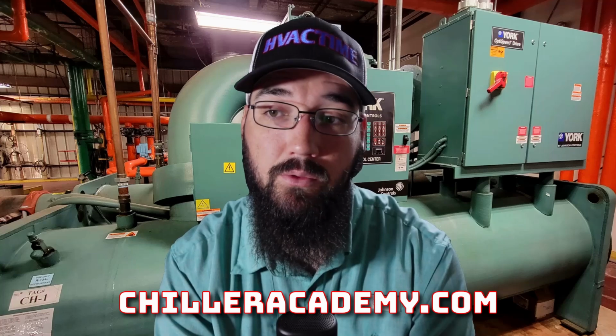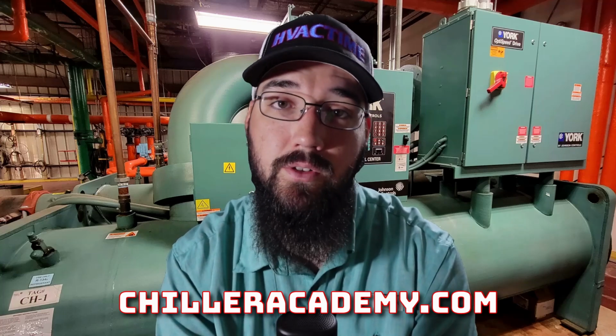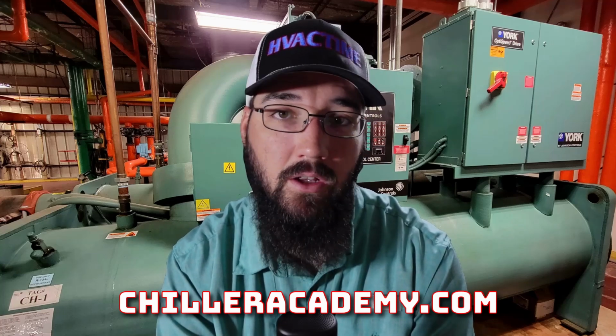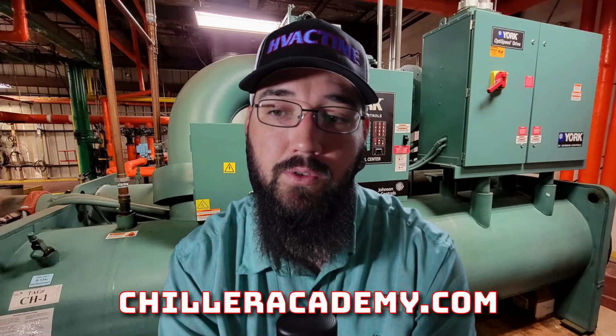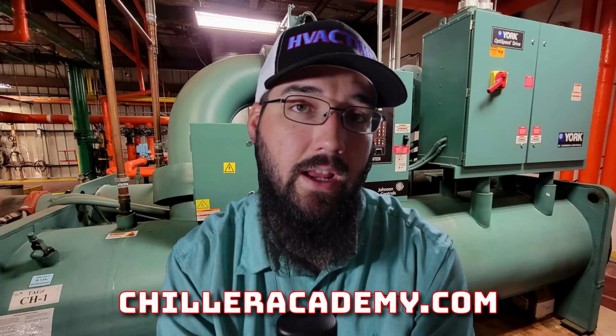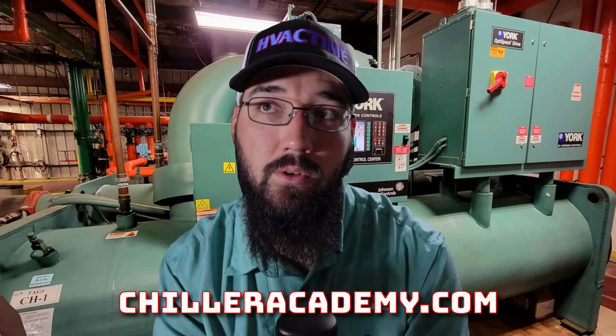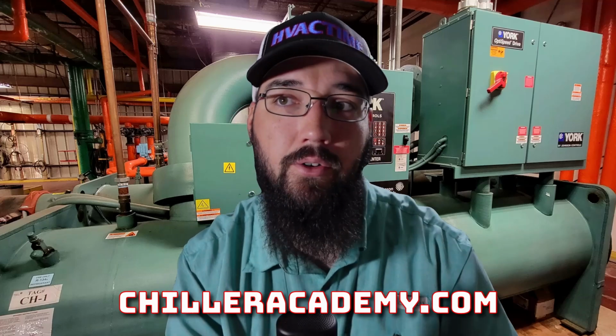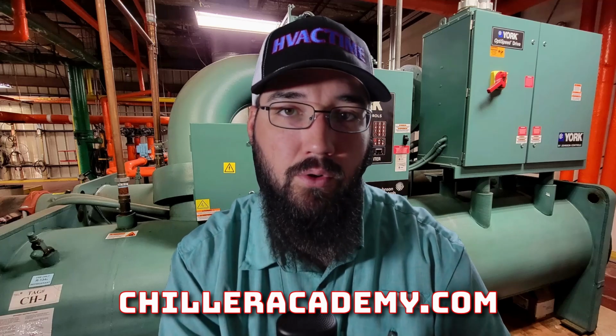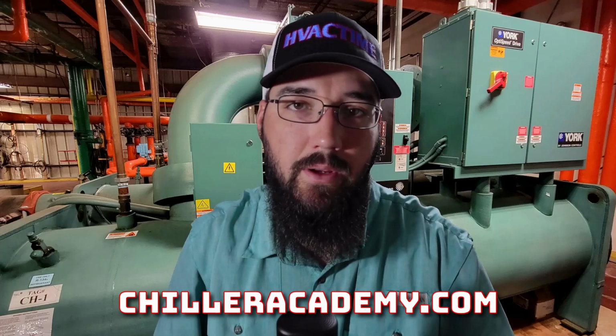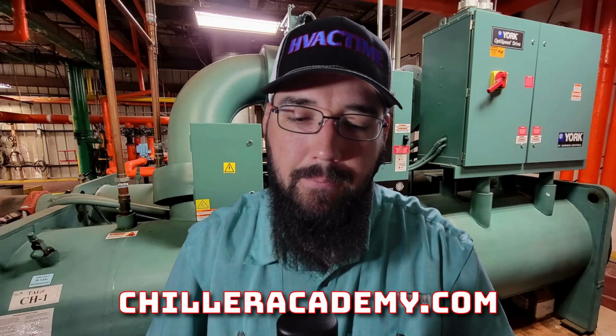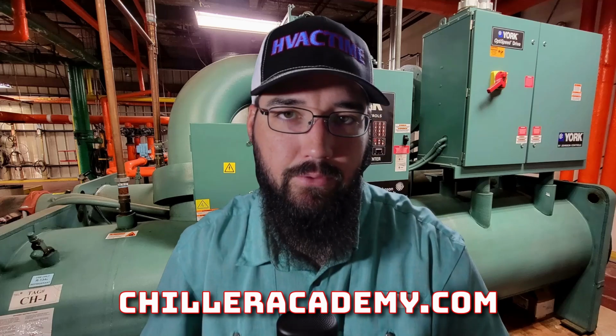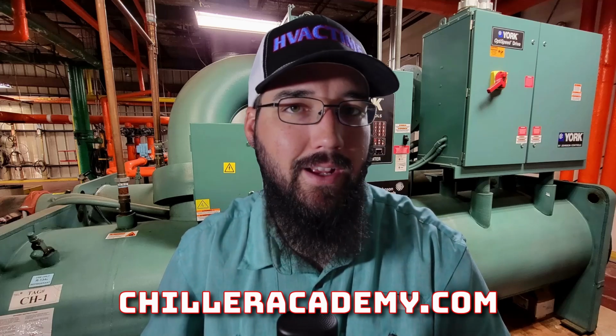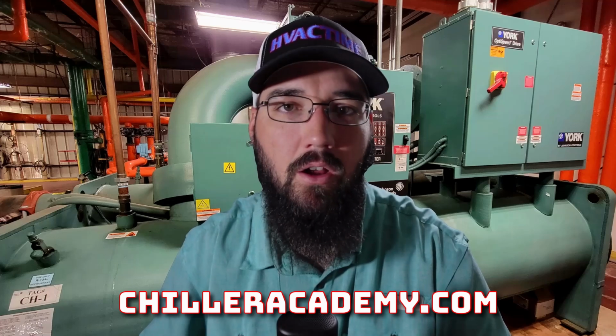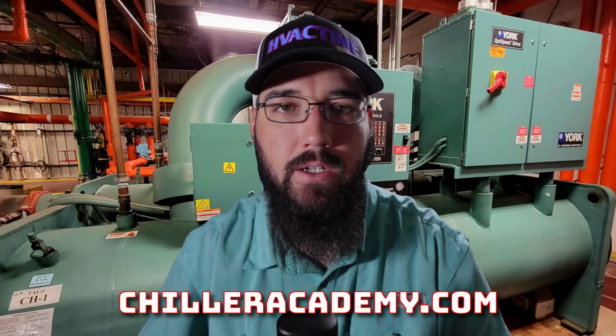In some of these cases, we're dealing with VRF systems that are hundreds of pounds of charge. It's not that uncommon to be sitting at, somewhere on the low end, 70 to 80 pounds. I've worked on systems that were over 200 pounds of refrigerant. Now, granted, it's pushing the limitations of what modern VRF technology can do, but these things are prone to leaks. Leaks are one of the major factors, and that's a lot of refrigerant to have to replace every time there's a leak that nobody caught for a long time, and you lost a large percentage of your refrigerant charge.